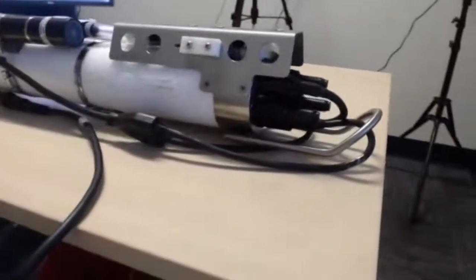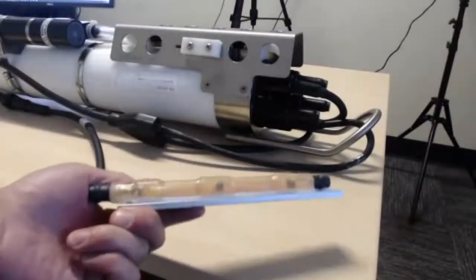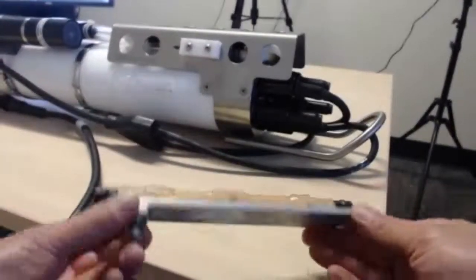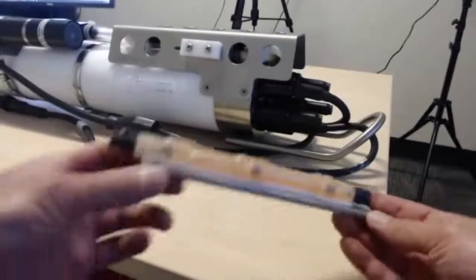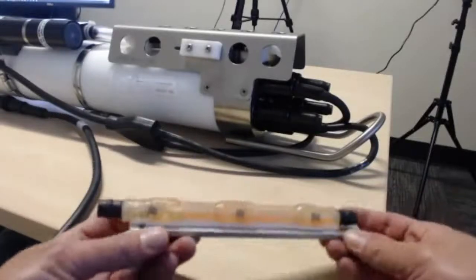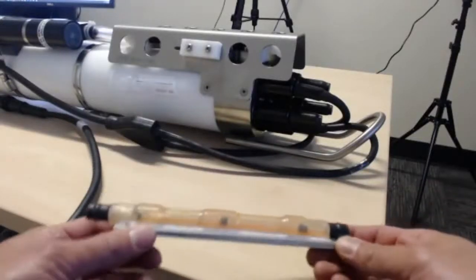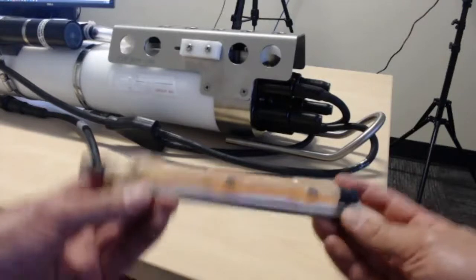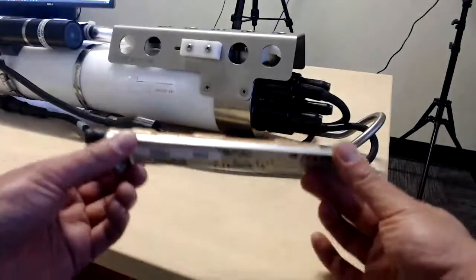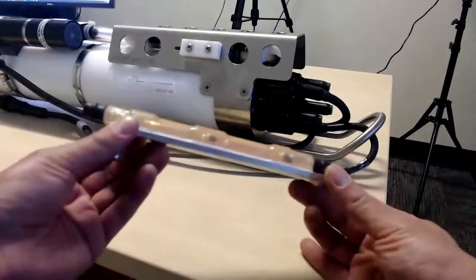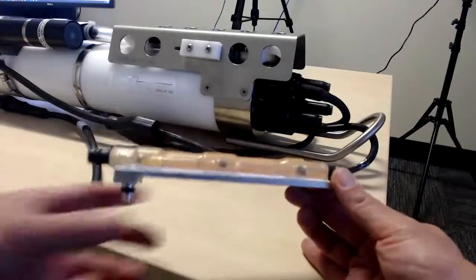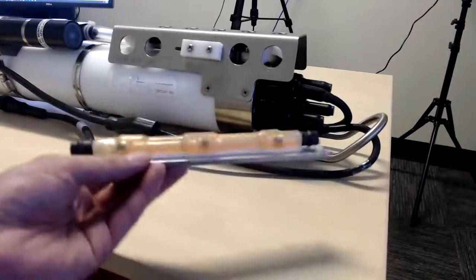The conductivity cell itself looks like this. This is actually maybe a microcat conductivity cell, but the point is it's a borosilicate glass tube with 3 electrodes inside of it. Because it's glass, it's pretty fragile. This is a precision scientific piece of equipment, and so we want to protect it. Hence the durable metal guard here.